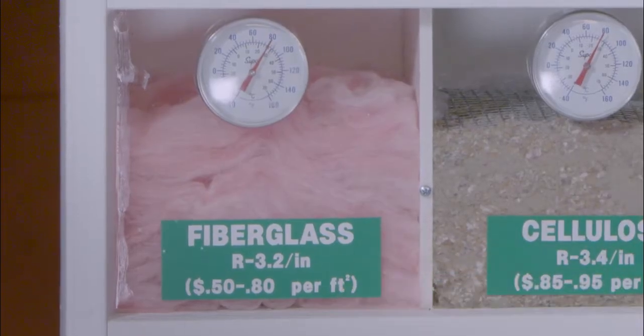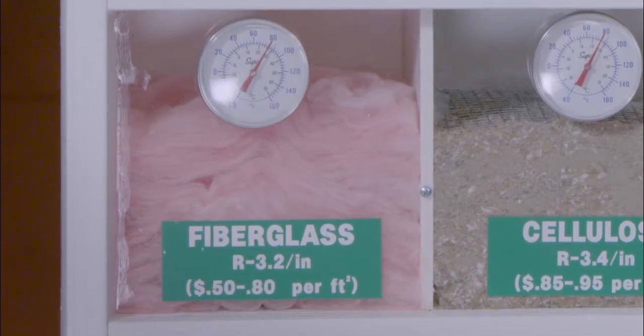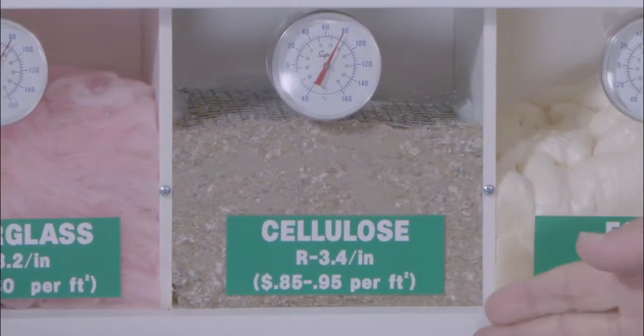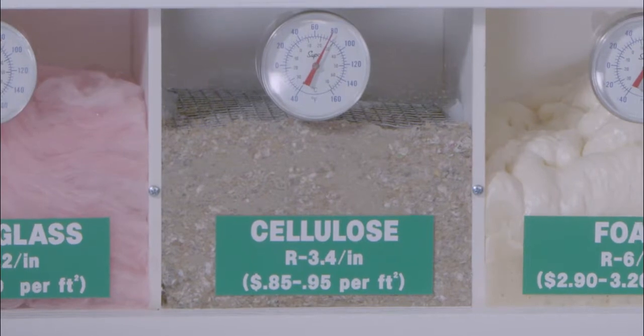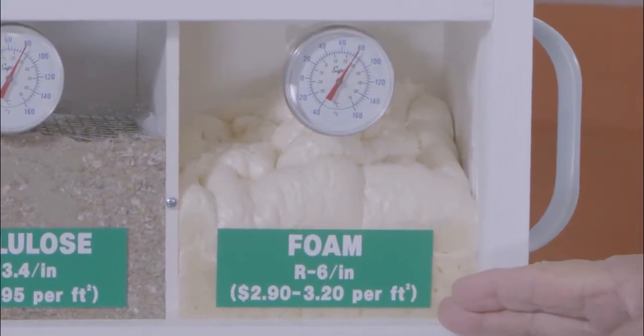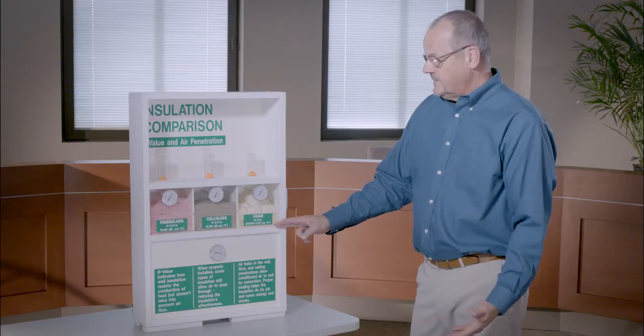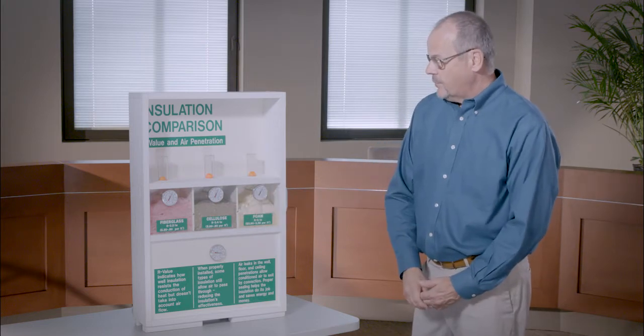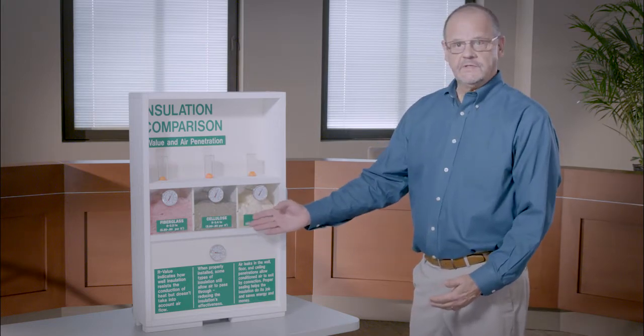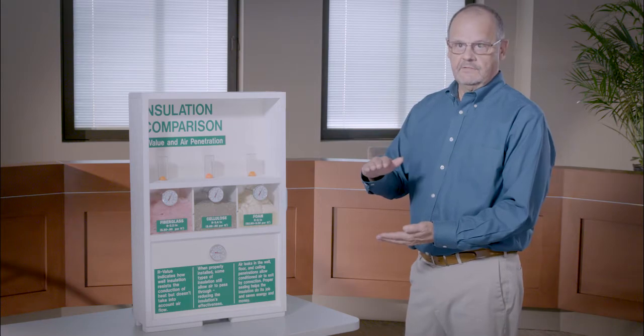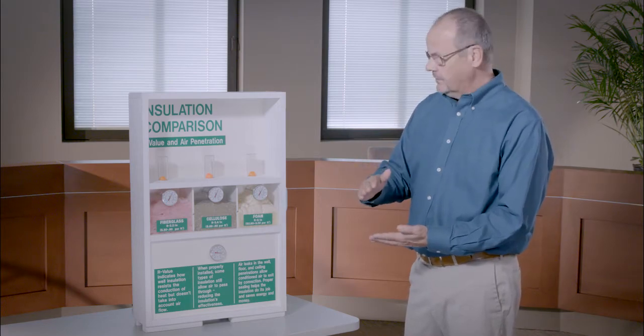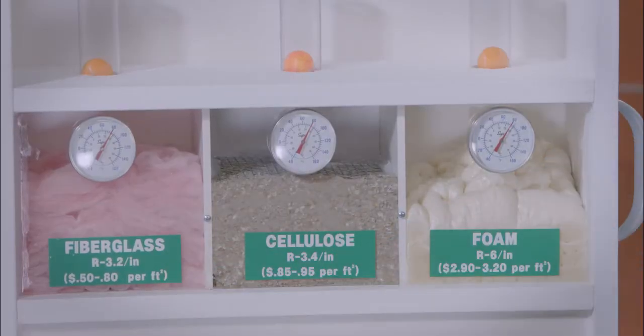Fiberglass, as shown here, gives you R 3.2 per inch, cellulose 3.4 per inch, and foam 6 per inch. What that means is you just simply have to put more fiberglass or more cellulose in to achieve your proper R value. So 38 is what we look for in this area, so it's just whatever choice that you want to make. They're all effective.